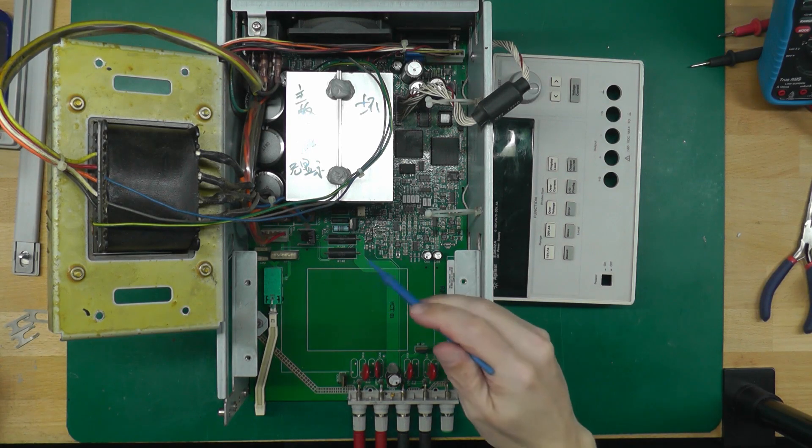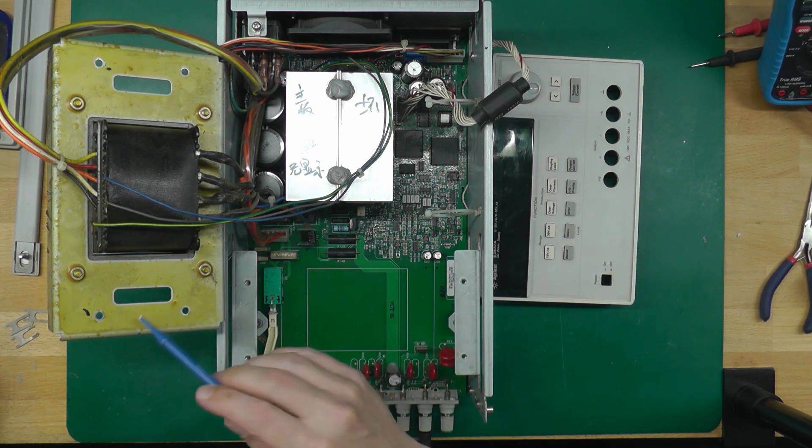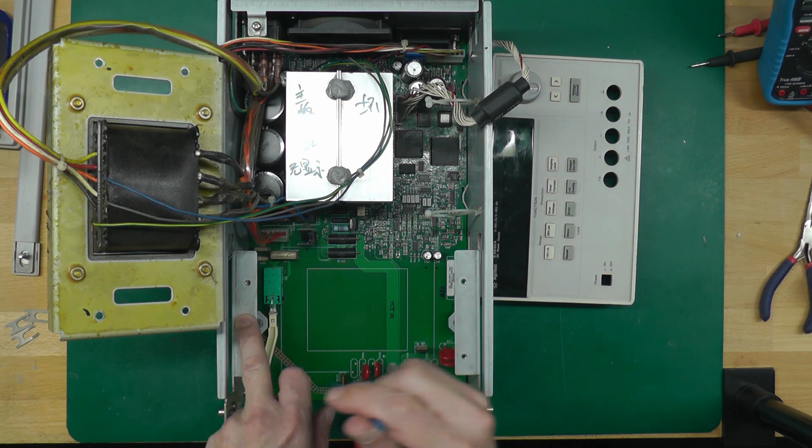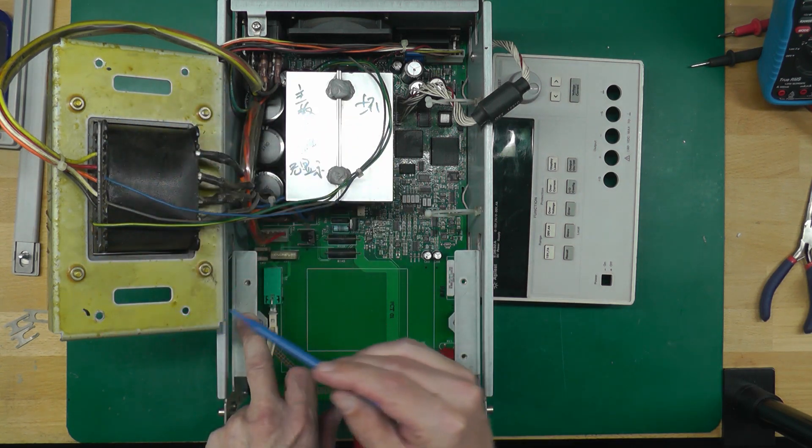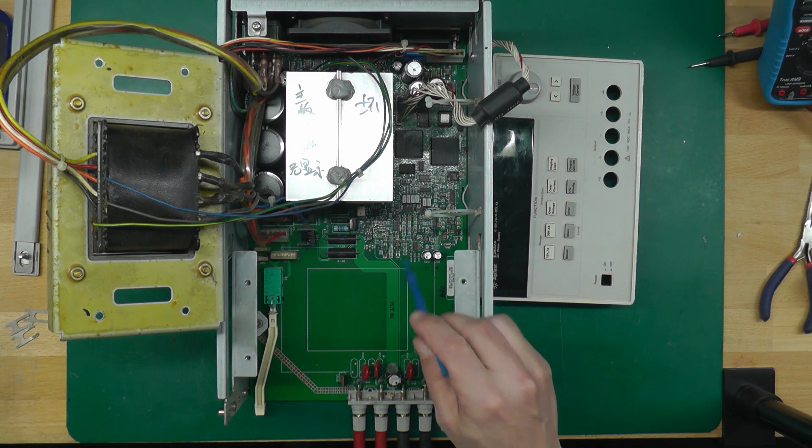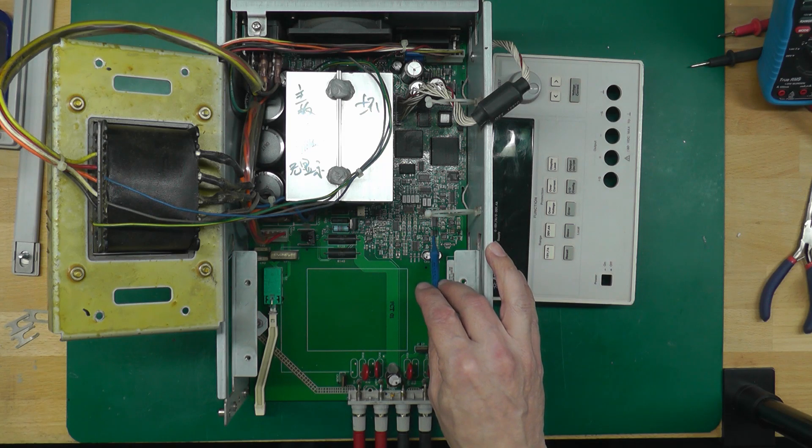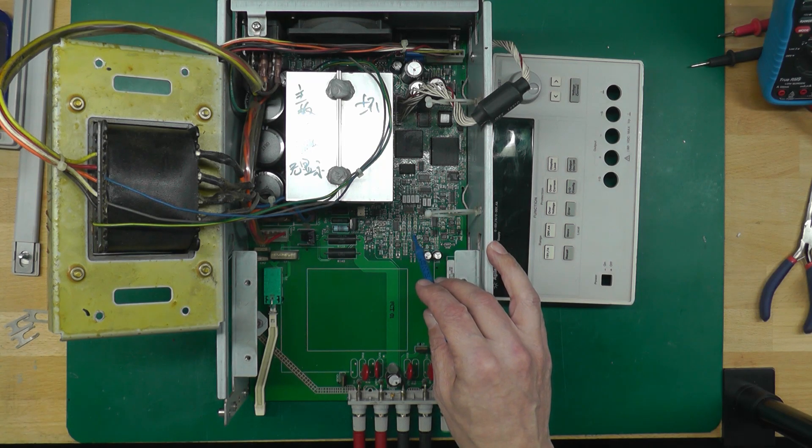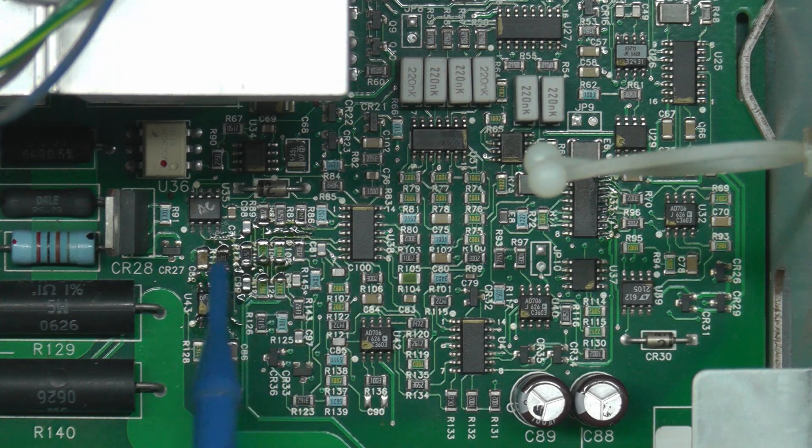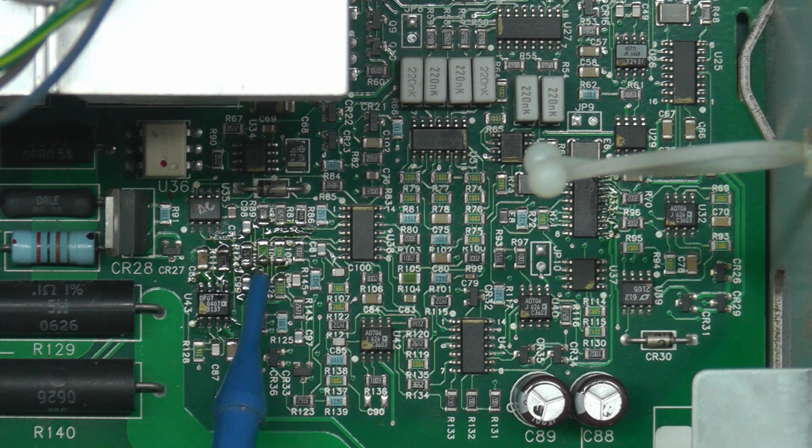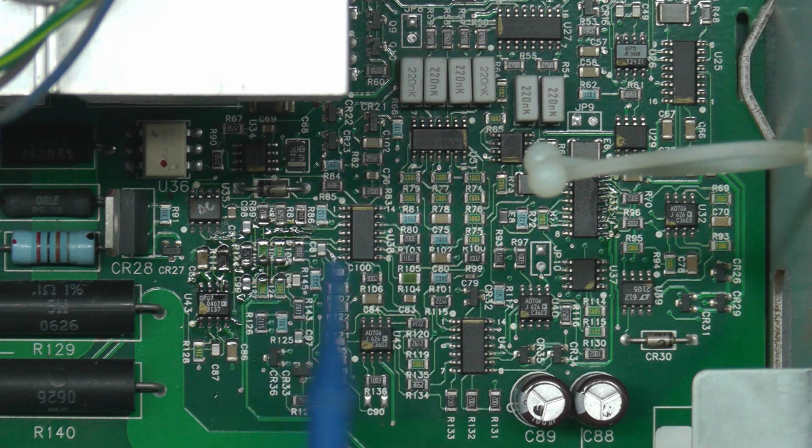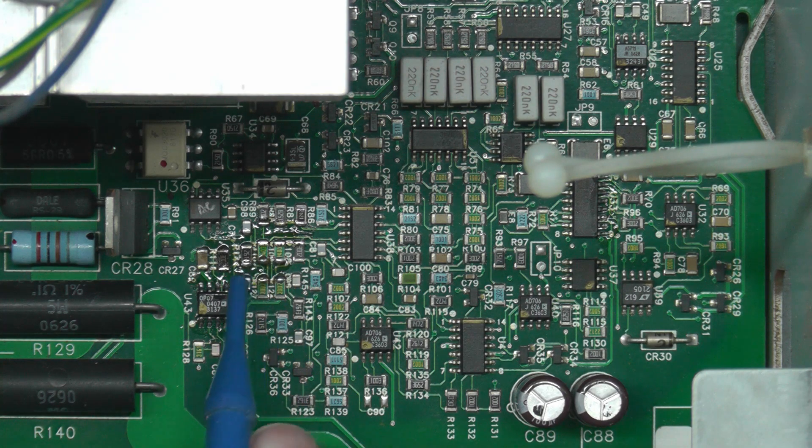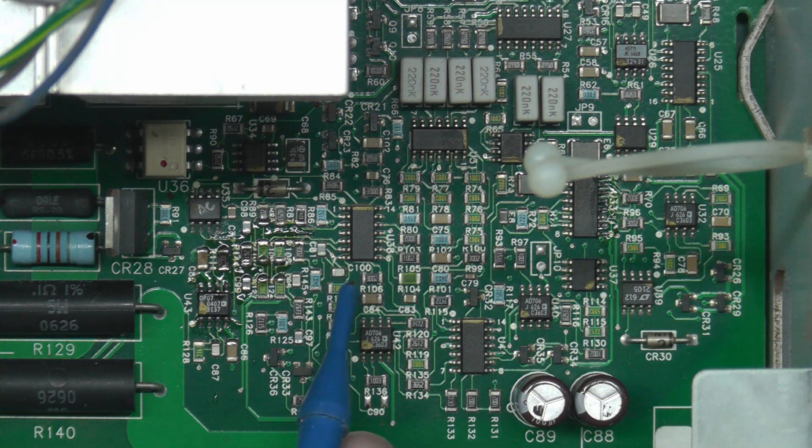From what I can see so far, somebody has been in here before. The screws that held down the transformer onto this top plate were slack, and the varnish residue was broken at all four points. So I think somebody had the transformer out. Down on the main board there is some flux residue round about some of the ICs and some of the resistors. A soldering iron has definitely been used here on those resistors and on this IC. Maybe someone's just had a bit of an attempt at trying to solve the problem by resoldering some joints.